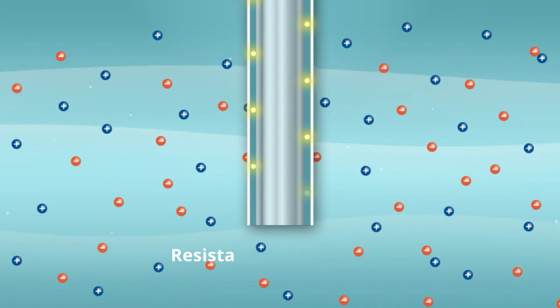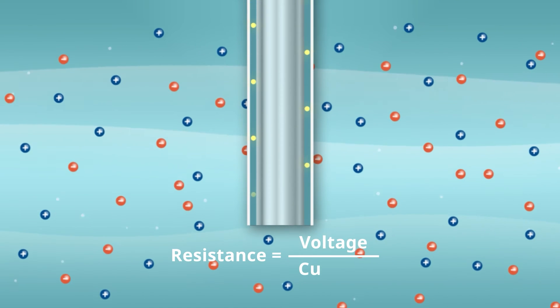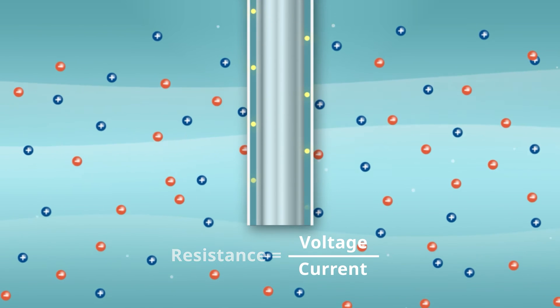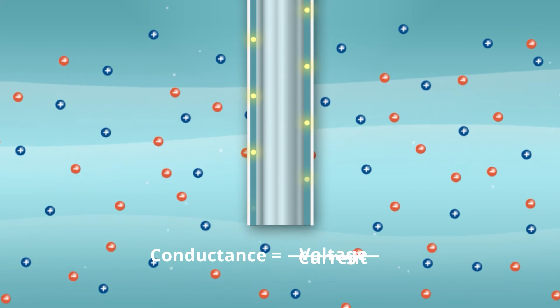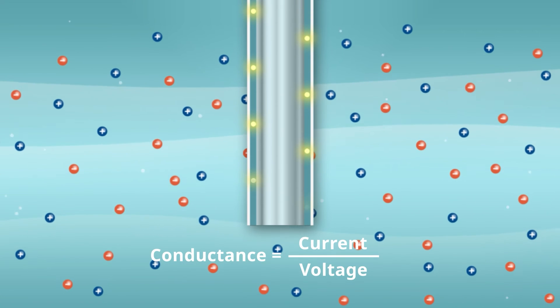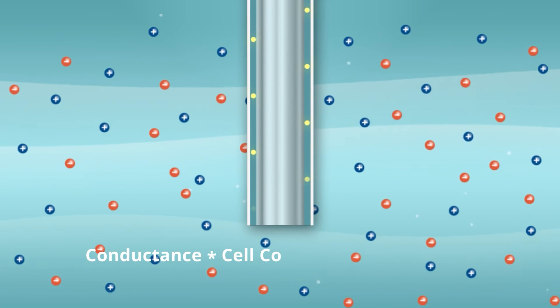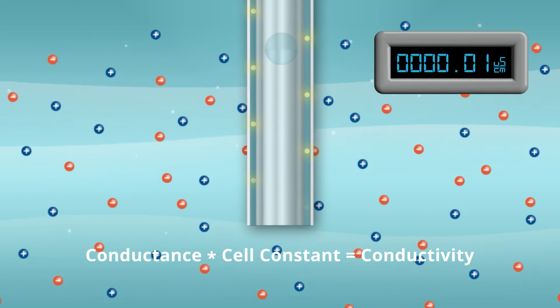The resistance is calculated by dividing the voltage by the current using Ohm's law. Conductance is then calculated by taking the reciprocal of the resistance. The product of the conductance and cell constant is the conductivity.